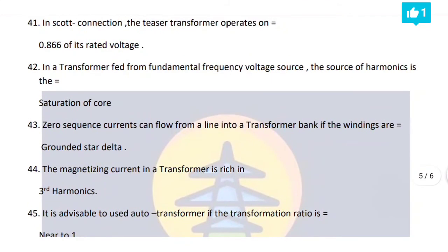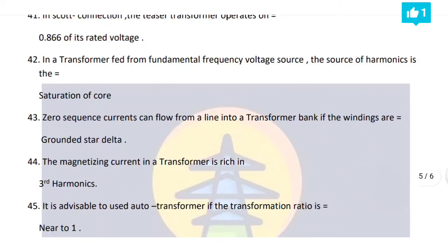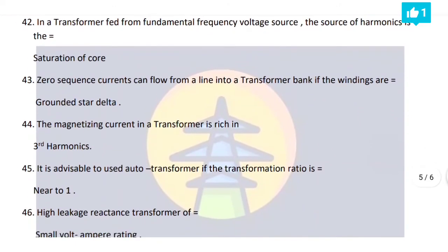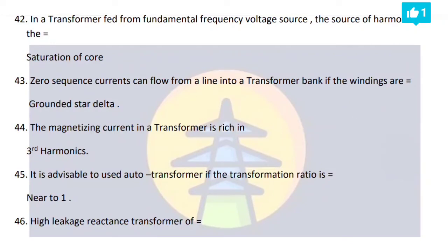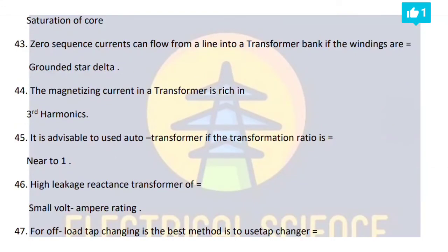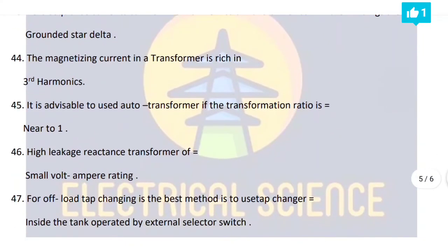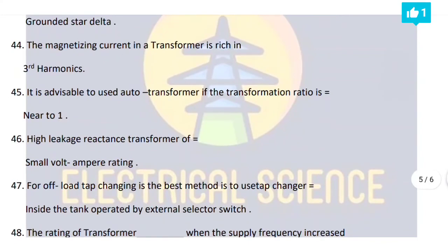42nd point, in a transformer fed from a fundamental frequency voltage source, the source of harmonics is the saturation of the core. 43rd point, zero sequence current can flow from a line into a transformer bank if the windings are grounded star delta. 44th point, the magnetizing current in a transformer is rich in, I repeat, the magnetizing current in a transformer is rich in third harmonics. 45th point, it is advisable to use an auto transformer if the transformation ratio is near to 1.